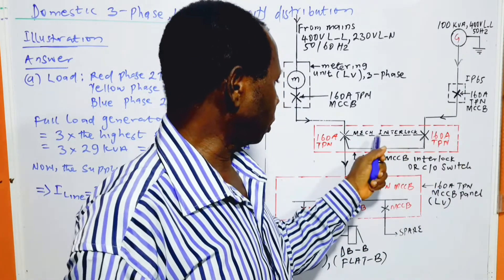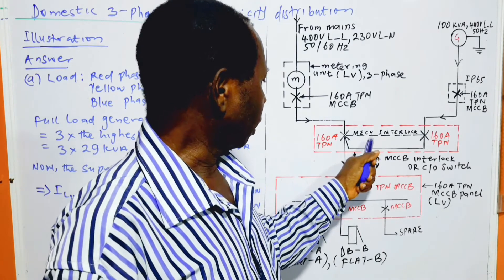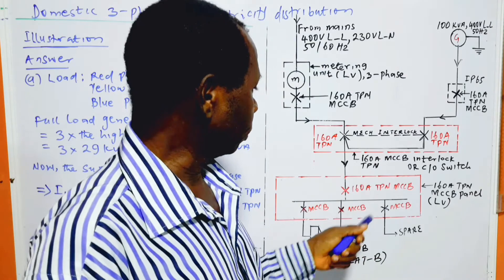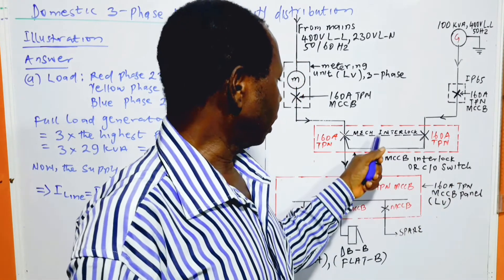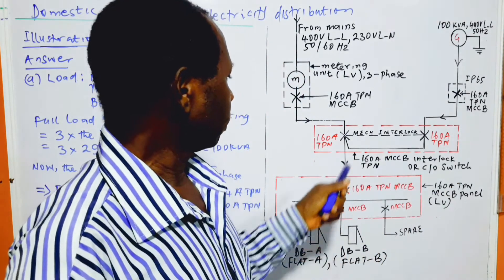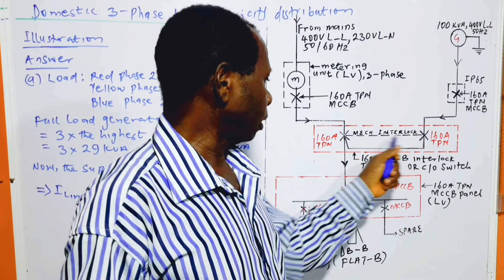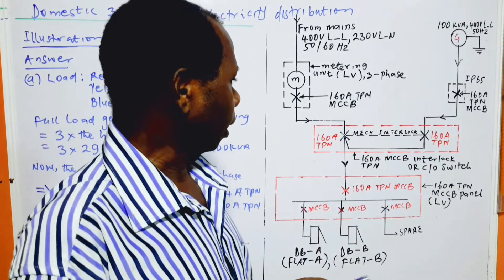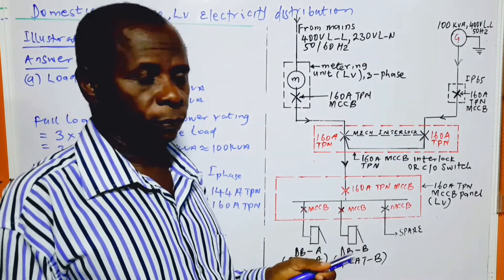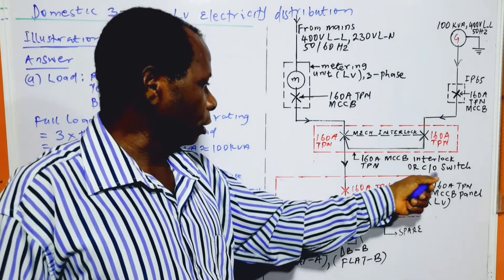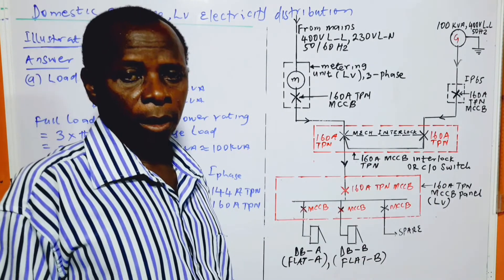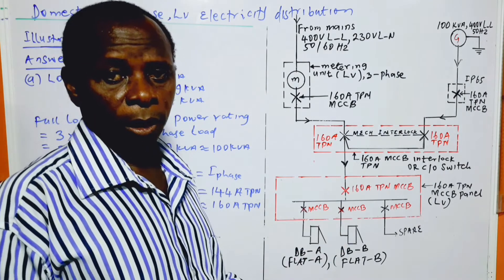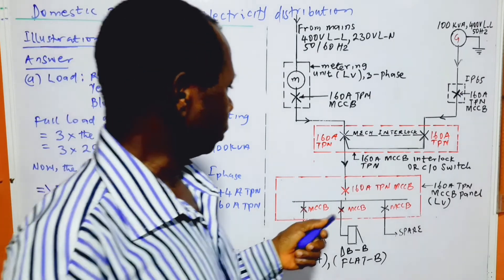I am using interlock here, mechanical interlock, but there is also an option of making use of changeover switch. But the advantage of using mechanical interlock like this is that these are circuit breakers and they can offer protective functions, unlike ordinary changeover switch which will not offer any protective function as it doesn't have any circuit breaker or any fuse inside it.